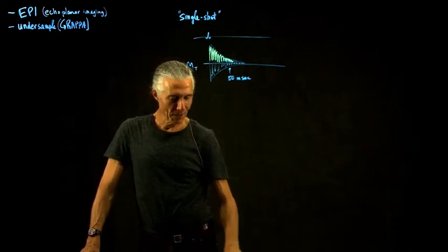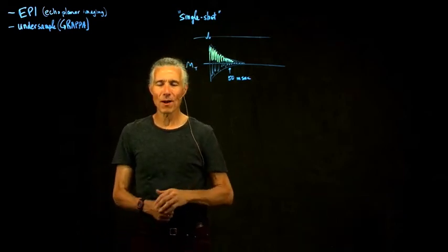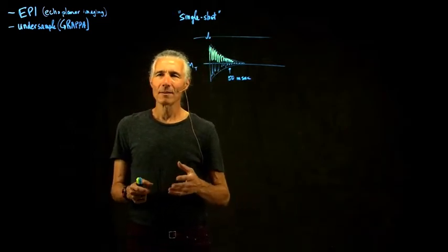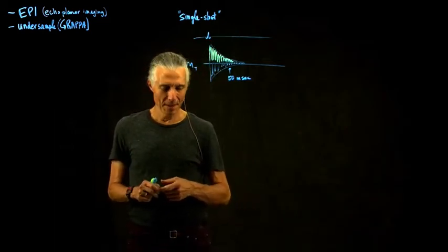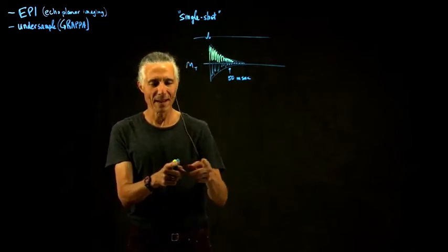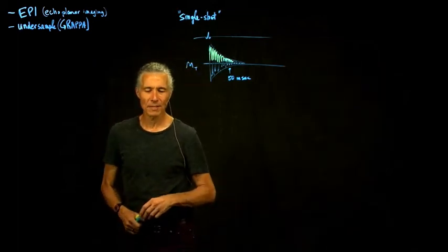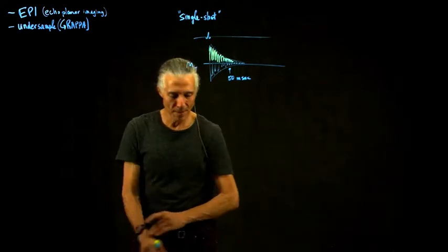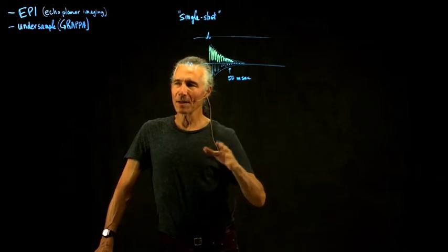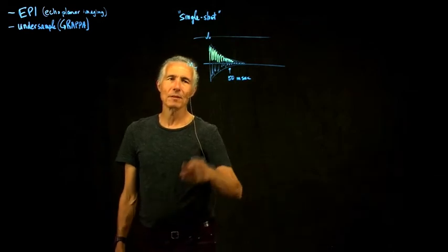And I always like to brag about the amplifiers. So now we have three 1.5 million watt amplifiers. They're kind of like a 3-channel stereo with 1.5 million watts per channel. The amplifier can put out 1,000 volts at 1,000 amps. That's 1 million watts. You need this very large amount of current going through the gradient coils in order to change them very rapidly and overcome the eddy currents. So that's the main reason that people couldn't do this.